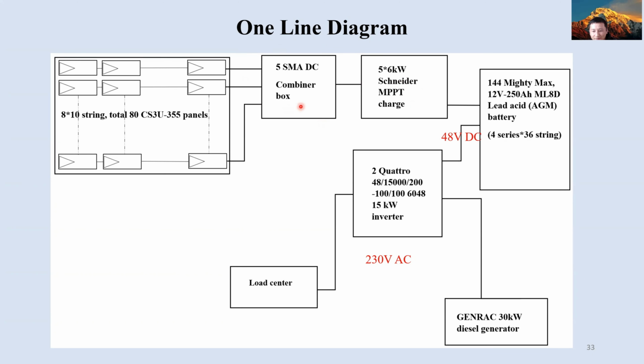This is the single line diagram of the system. We have 10 strings of 80 panels with a rating of 355 watt for each module. These 10 strings go to the 5 combiner boxes, 2 strings per combiner box. Then the DC energy goes to the 6 kilowatt Schneider MPPT charge controller and to the battery storage system of 4x36 strings of 12 volt 250 ampere hour Mighty Max batteries. Then this DC energy is converted into AC energy by the 2 into 15 kilowatt Quattro inverters, and then supplied to the load.